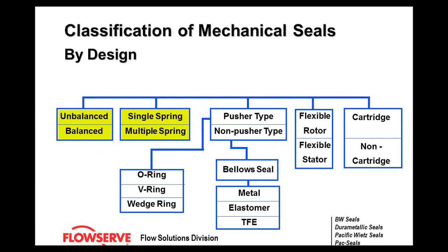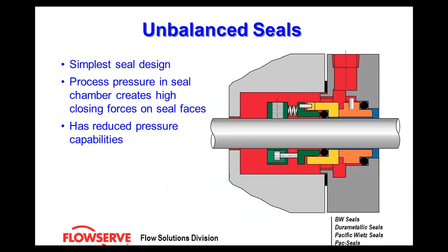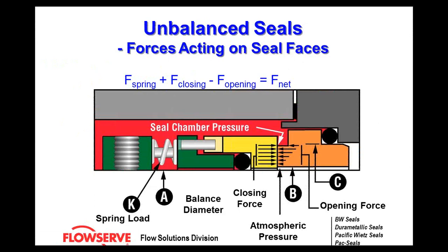Now we'll talk about balance versus unbalance, and multiple spring versus single spring. Unbalanced seals are the simplest designs — you'll see them in internally sealed devices like dishwashers or washing machines. The process pressure in the seal chamber creates high closing forces on the seal. These have reduced pressure capabilities.